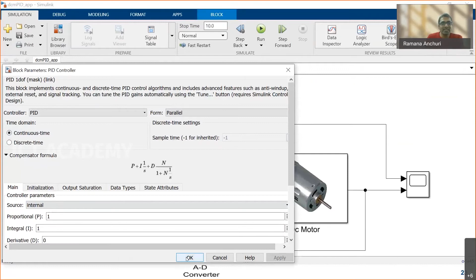Okay. So this is the response now. Now, if you observe clearly, the motor is not settling at a speed. It's taking a relatively long time, and even when the load is applied, the speed dropped very much, right? And it is not able to catch up to the reference speed. So right now, these PID gains don't work for this motor. Now, what you can do is double click on the PID, and you have an option to tune the PIDs, right?